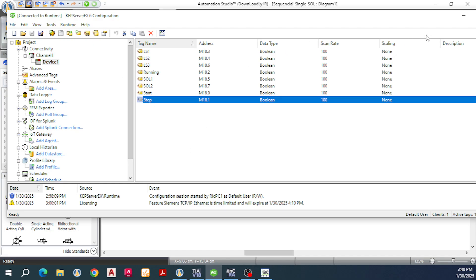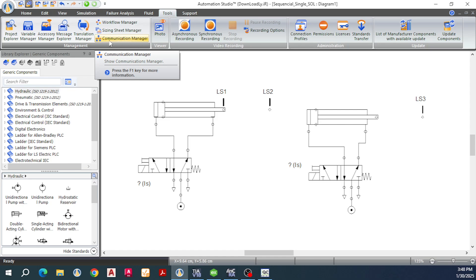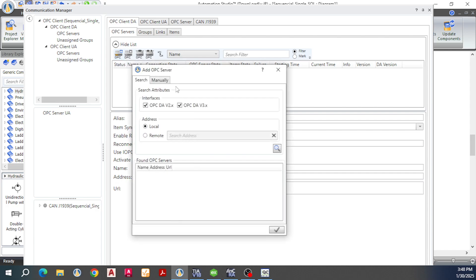After you create the tags, go back to Automation Studio and then go to Tools. Here we have the Communication Manager — click on it. First, select OPC DA client and then OPC server. Next, click here to add an OPC server. A pop-up window will appear. I will check OPC DA version 2x and version 3x, then select Local and click the Search Local OPC Server button.